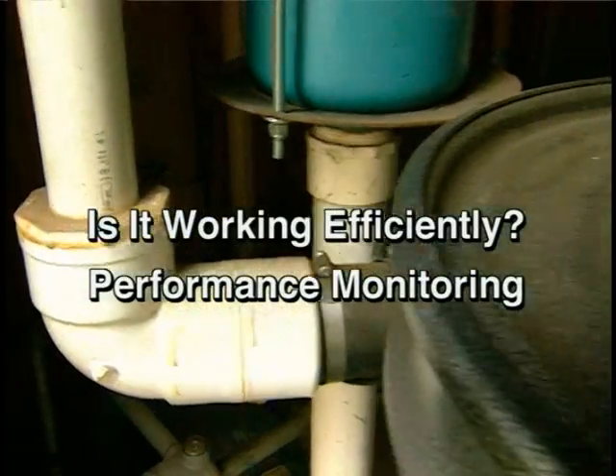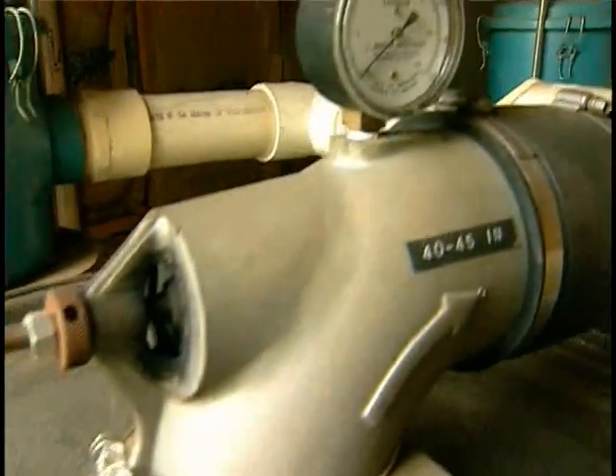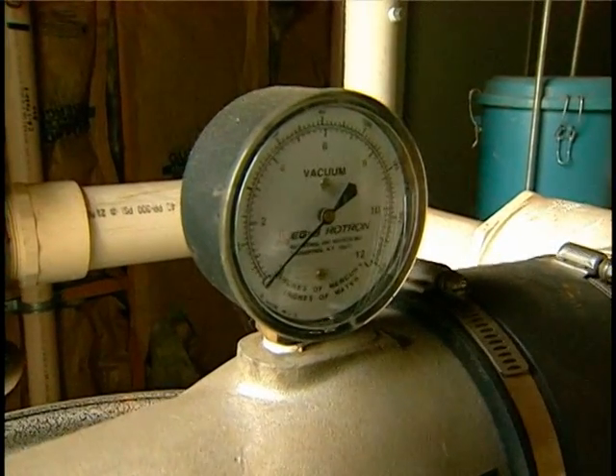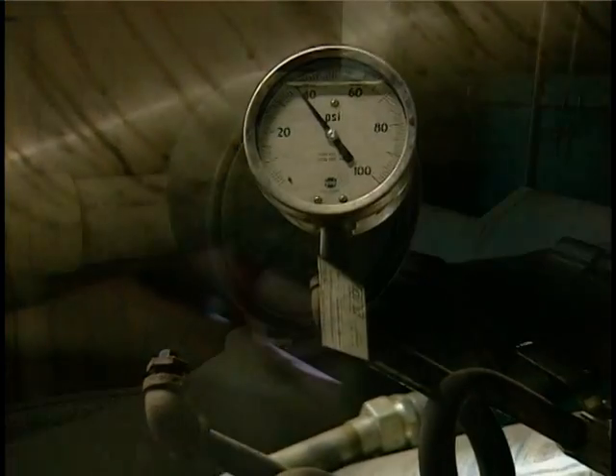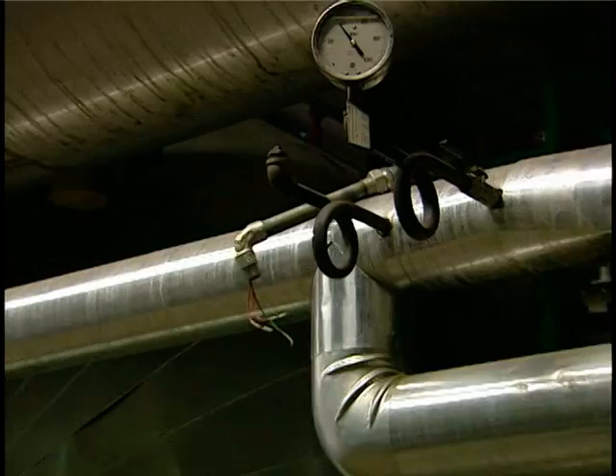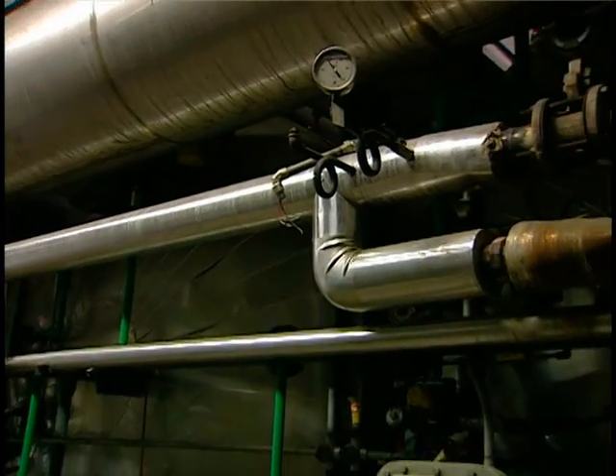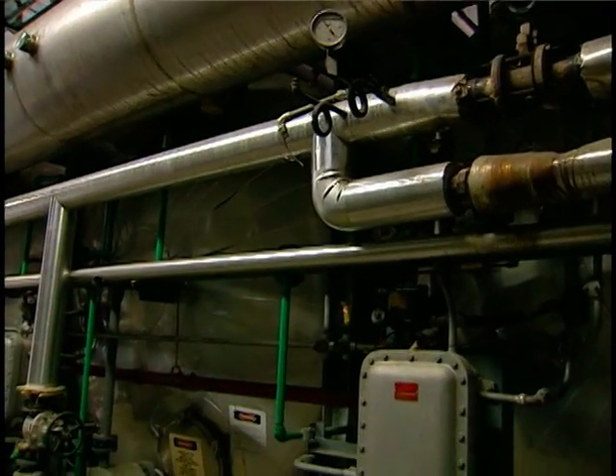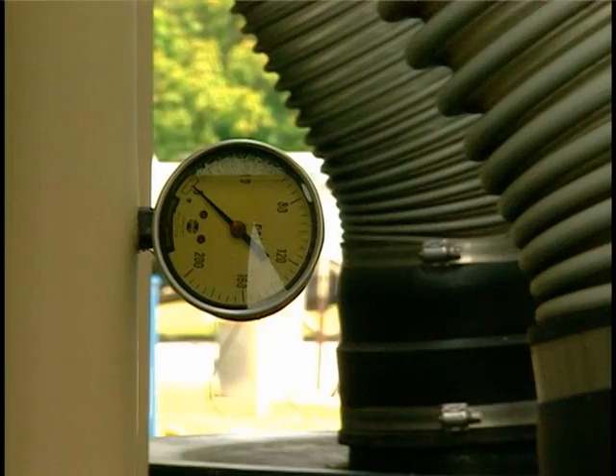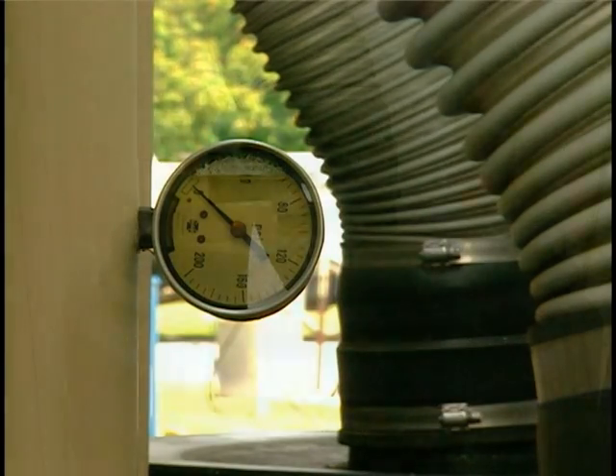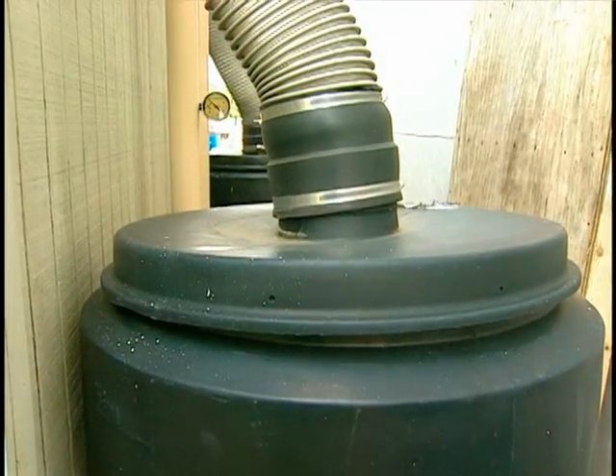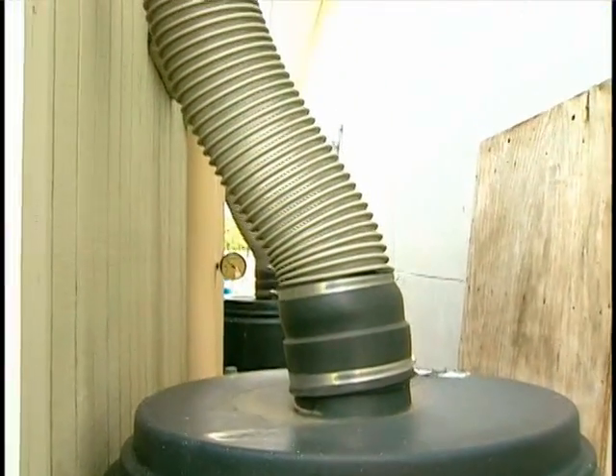The ability to evaluate potential problems during a field inspection will depend on how well the system is instrumented. Most large activated carbon systems are well instrumented. However, smaller systems may have limited instrumentation. Performance evaluation of these systems will be difficult unless measurements of important parameters are made.